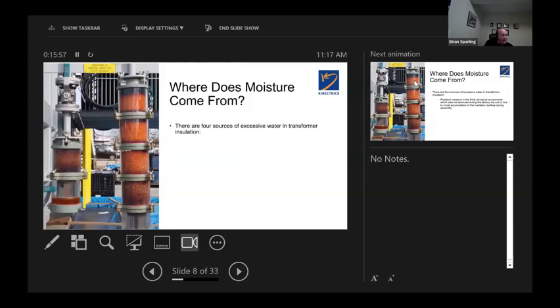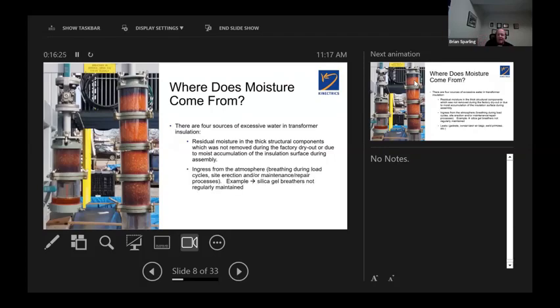So that begs the question, where does it come from? There are four main sources. Part of it is the residual moisture in the thick structural components, which was not removed during factory dryout, or moisture accumulation on the insulation surface during assembly in the factory or on site. And typically that's not a big factor, because if the moisture is in those thick structural components, we're not that worried because the moisture is going to be locked up there. It's never going to move.